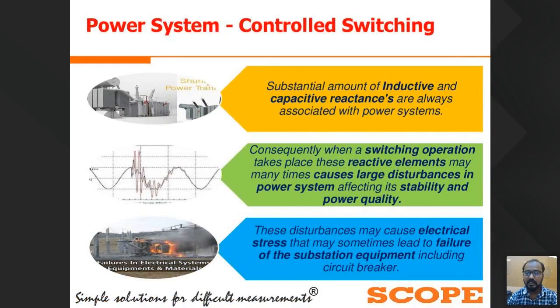As we all know, a substantial amount of inductive and capacitive reactive loads are always associated with our power system. The examples are the shunt reactor, power transformer, capacitor banks, and transmission lines. When we switch this type of reactive element, it may cause large disturbances in our power system. At the time of random switching of these reactive elements, they create large switching surges in the power system. These large switching surges, disturbances, and switching transients will affect the system stability as well as the power quality of the power system network. So, to minimize these switching transients and switching surges, we are using the control switching device.